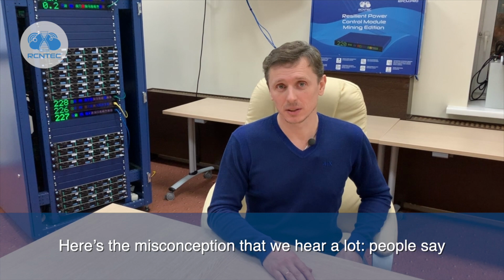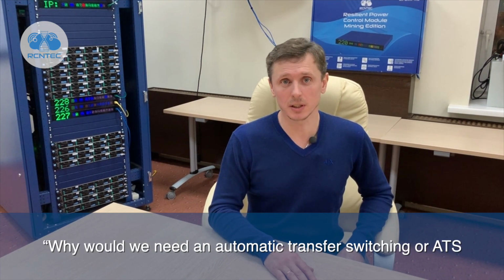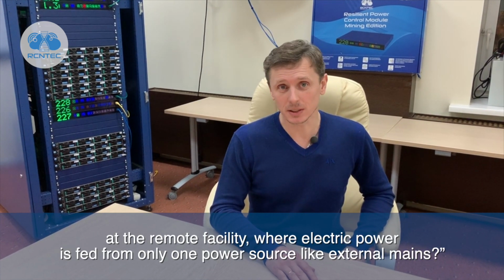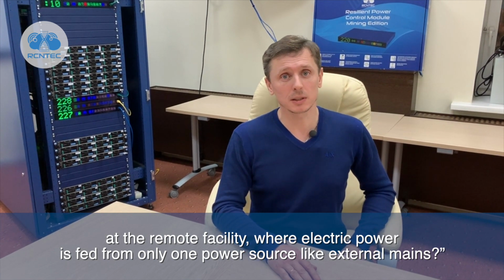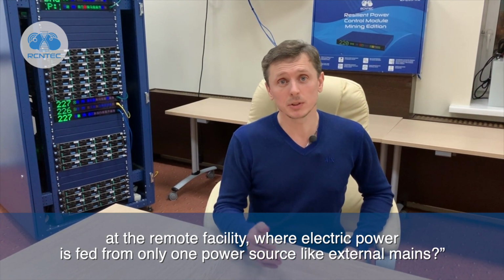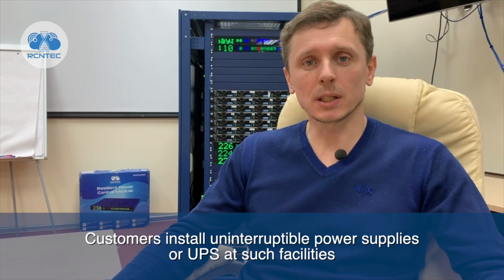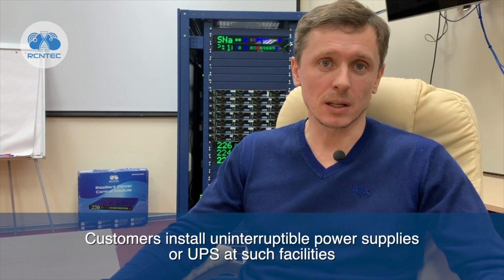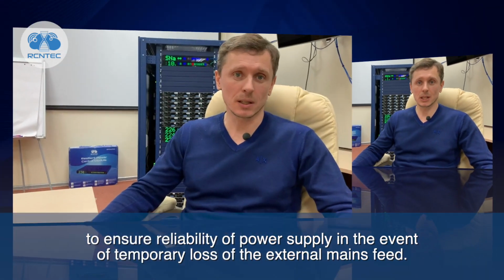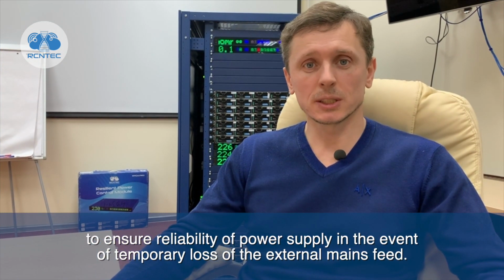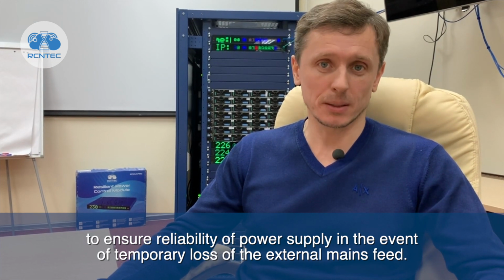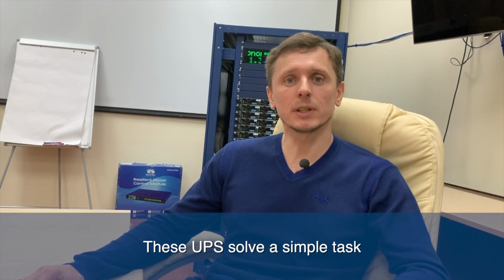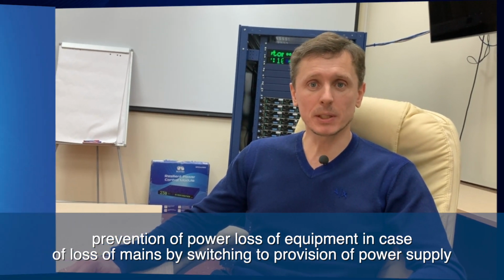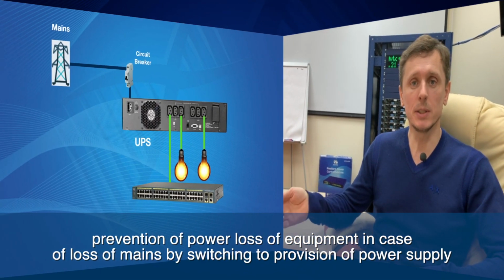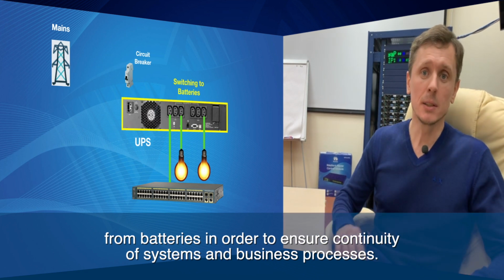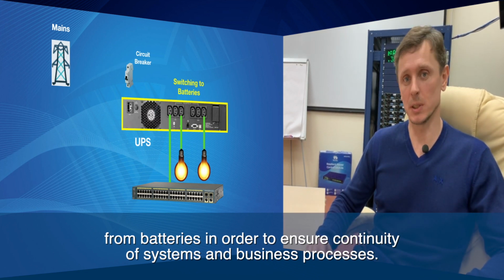Here is the misconception that we hear a lot. People say, why would we need an automatic transfer switching, or ATS, at the remote facility where electric power is fed from only one power source like external mains? Customers install uninterruptible power supplies, or UPS, at such facilities to ensure reliability of power supply in the event of temporary loss of the external mains feed. These UPS solve a simple task: prevention of power loss of equipment in case of loss of mains by switching to provision of power supply from batteries in order to ensure continuity of systems and business processes.